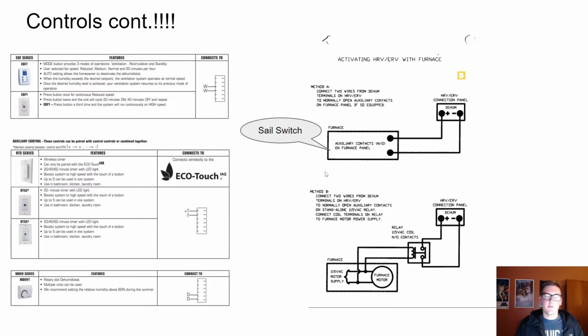And so the wiring is probably going to be specific per ERV, but for that example, for my Fantech ERV, you wire that to the two H plus and H minus. This ERV has 3 different wiring harnesses you can use, and so that's what I did on one of those. So maybe it's a good idea if you had the same ERV.